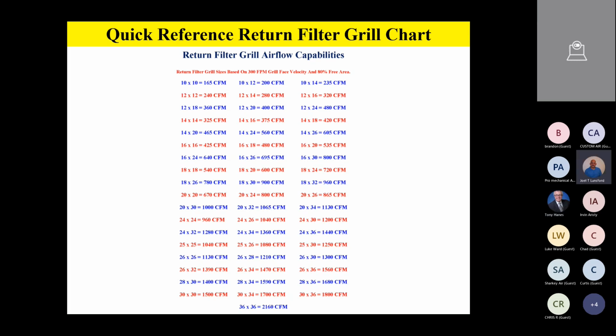So, to Tony's point real quick too, the 80% free area is an average that I used when I developed this chart. That's an average of all different return grills that we happen to have in our inventory. I generated this back when I was in distribution myself. So to Tony's point, if you go to Hart and Cooley or Cook or whoever, and you look up a particular return grill, it may say something like K of C or K of A, and it might be 92%. So instead of using a 0.8 in the formula, you'd use a 0.92. So that 80% free area is just an average of grills that we had in stock. We just averaged them up as far as the K of A.